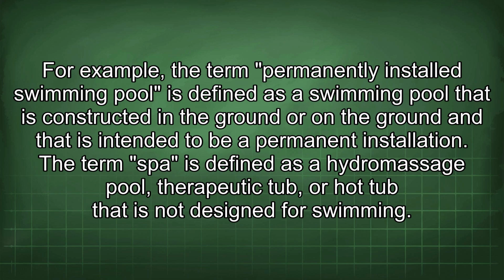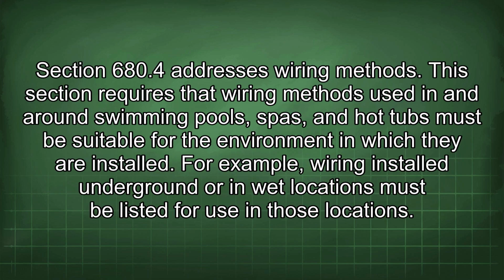For example, the term permanently installed swimming pool is defined as a swimming pool that is constructed in the ground or on the ground and that is intended to be a permanent installation. The term spa is defined as a hydromassage pool, therapeutic tub, or hot tub that is not designed for swimming. Section 680.4 addresses wiring methods. This section requires that wiring methods used in and around swimming pools, spas, and hot tubs must be suitable for the environment in which they are installed.